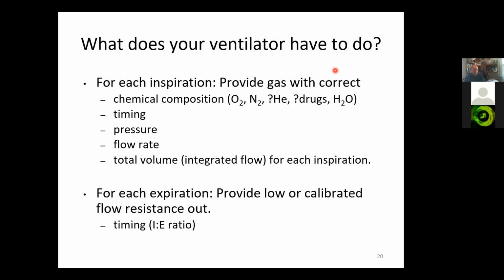And then finally, for expiration, there has to be a path out of low resistance to atmospheric pressure. Now, it may be that you can vent your patient's exhaled gas to the atmosphere right there. If your patient's otherwise healthy, isn't spraying out COVID virus, isn't spraying out anesthesia drugs, then an ICU ventilator can vent right out to the room, and it isn't a hazard to anyone there. But it may have to be actively evacuated and brought outside the building for infectious causes, or trapped and processed for pollution causes.